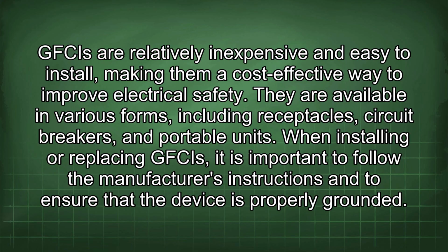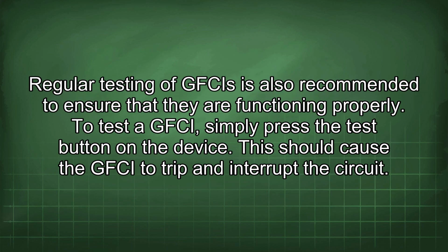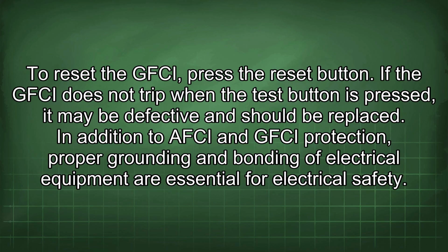When installing or replacing GFCIs, it is important to follow the manufacturer's instructions and to ensure that the device is properly grounded. Regular testing of GFCIs is also recommended to ensure that they are functioning properly. To test a GFCI, simply press the test button on the device. This should cause the GFCI to trip and interrupt the circuit. To reset the GFCI, press the reset button. If the GFCI does not trip when the test button is pressed, it may be defective and should be replaced.